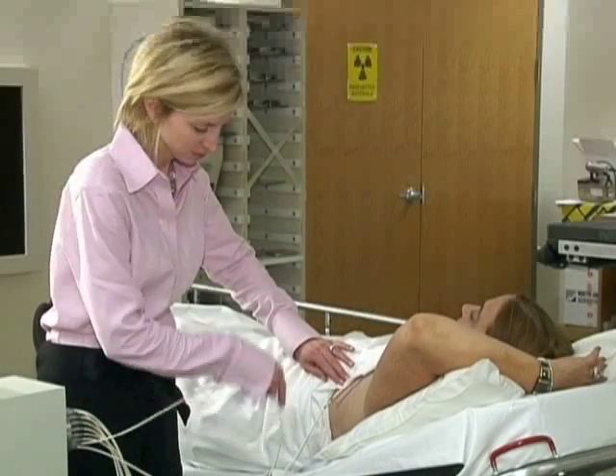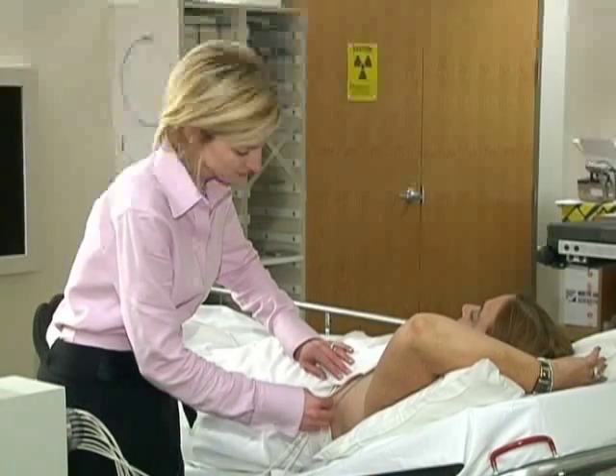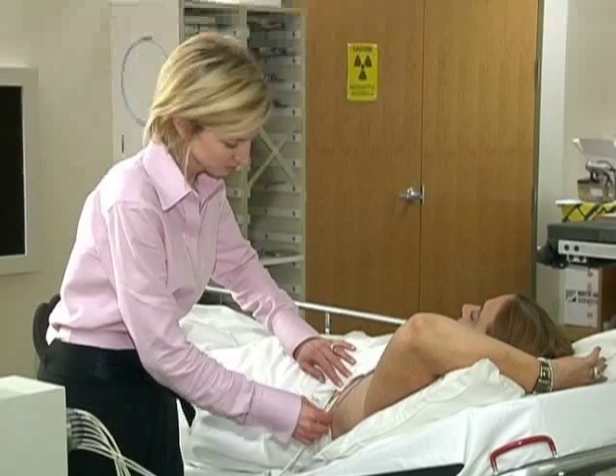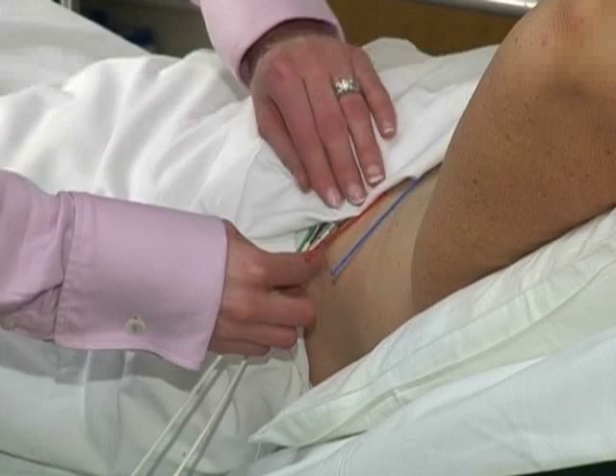When you come in for the treatment, you come to the specialized vault that we have, which has thick concrete walls for shielding, and we lie you on a comfortable bed. We will then hook up your catheters to a series of cables that emanate from a machine that has the radioisotope within it. At that time, I will tell you the length of time for the treatment, which is usually 5 to 10 minutes. And then we will leave the room after a series of checks, which are somewhat complicated for the first treatment. It may last for 5 or 10 minutes. And then we'll turn on the machine and actually deliver the first treatment.